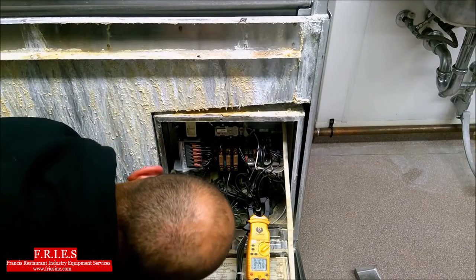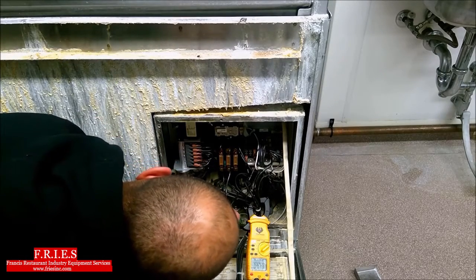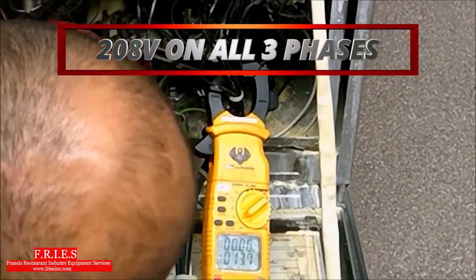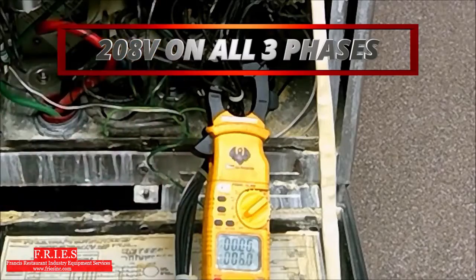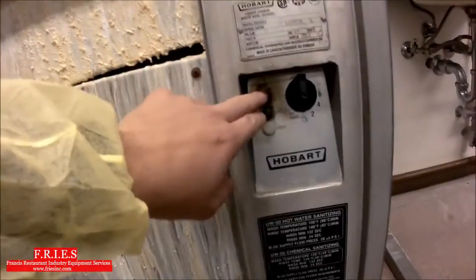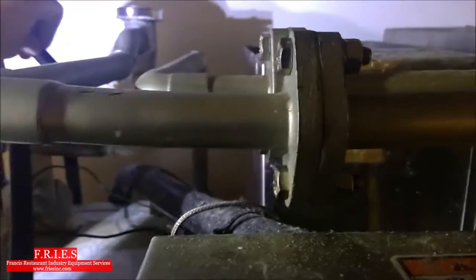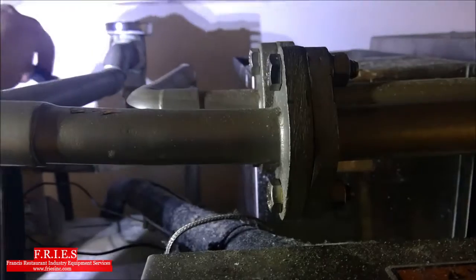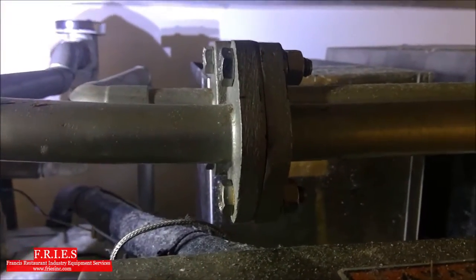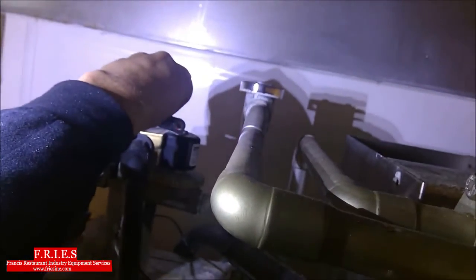Alright, so first thing we're going to do is check incoming power. It is 3-phase. Alright, so we do have 208 on all 3 phases. Next thing I'm going to do, I'm going to fire up the unit. And let's fill the unit first of all. So you can see here that the solenoid is getting power. You can see my magnetic field detector there is spinning. And you can hear the unit as well, it's filling. So the unit is full.